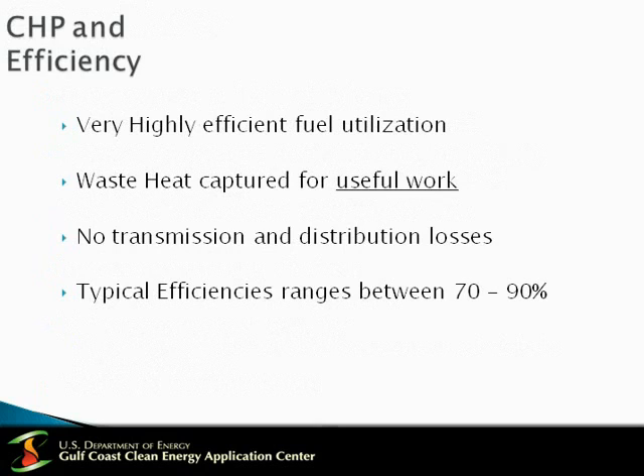Now, to look at why CHP is efficient, basically you have very high efficient fuel utilization. The waste heat is captured for useful work. You don't have the transmission and distribution losses that are typically associated with the grid, and your efficiencies range between 70 to 90%.